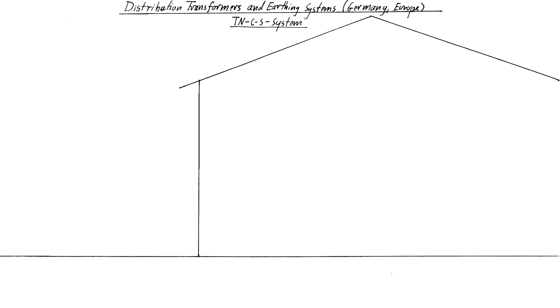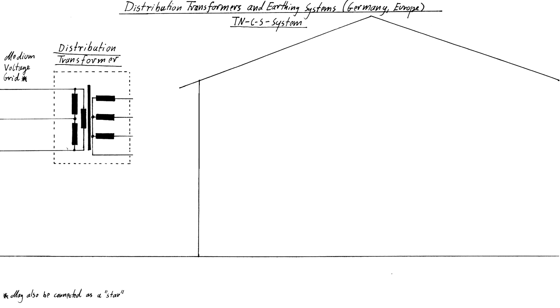to my electrical outlet. The local distribution transformer's primary side is connected to the medium voltage grid. The primary windings are often connected in a delta configuration, while the line is not carrying a neutral conductor at all. The transformer then steps the voltage down to the 400 volt level, with the secondary windings connected in a star point configuration. The star point is then connected to the earth near the transformer, constituting what is called Betriebserde, for which I chose the English translation system ground.